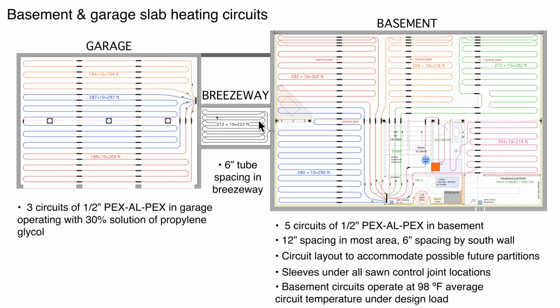There's a circuit in a breezeway here. You can see that's close tube spacing because there's a higher ratio there of wall area to floor area. It's a space that would lose heat faster. And then the garage is actually set up for floor heating as well. All those circuits in the garage operate with an antifreeze solution through a heat exchanger, so the owner can just turn those circuits right off if they don't want to heat the garage, and nothing's going to freeze. Again, you can look at all these in more detail, and I would encourage you to do that in the PDF file.